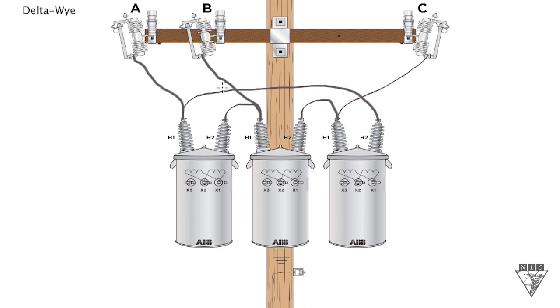So what we made here with a delta primary connection, this is a phase-to-phase connection for the transformers. So what I mean is if you look at this H1, it goes up to A phase. If you look at the H2 on this transformer, it's tied over here and then goes to B phase. So this transformer is connected to A phase and B phase.